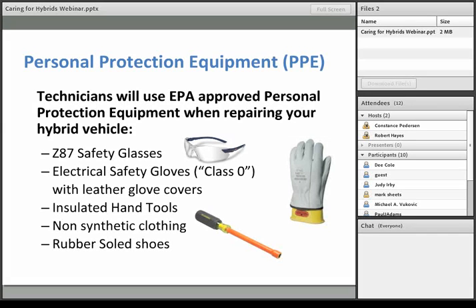They're also going to use electrical safety gloves, class 0. These gloves are highly resistant to electric current flow, and they also use leather gloves placed over the top of the rubber gloves to prevent the rubber gloves from being punctured. The rubber gloves need to be tested every 6 months for resistance, to make sure you will not have any electrical shock.